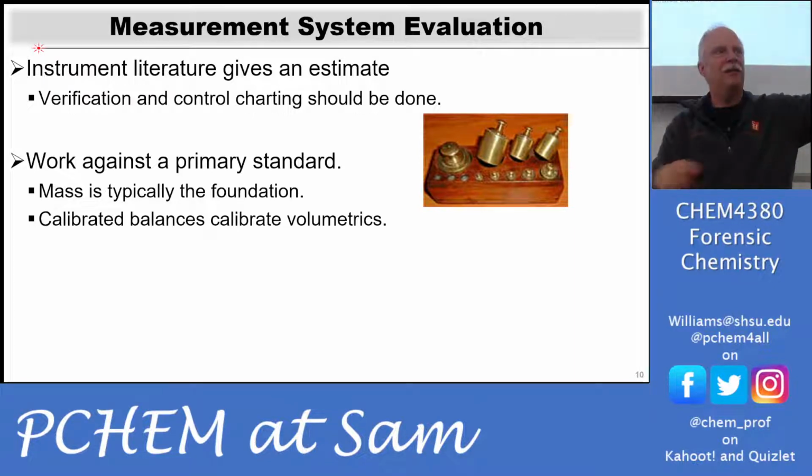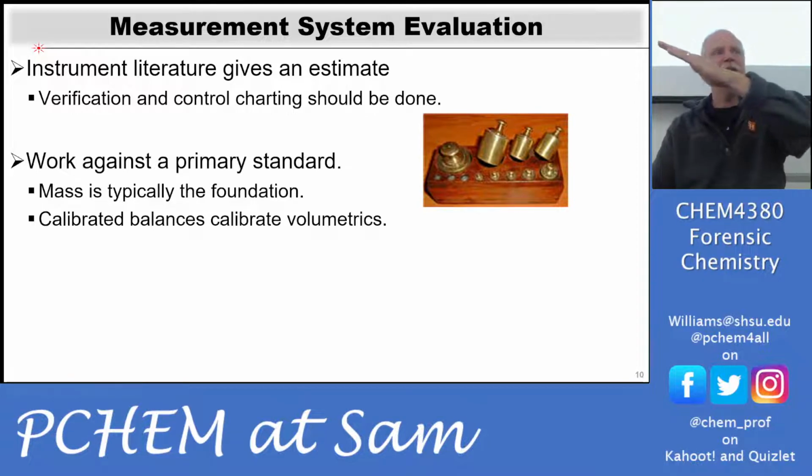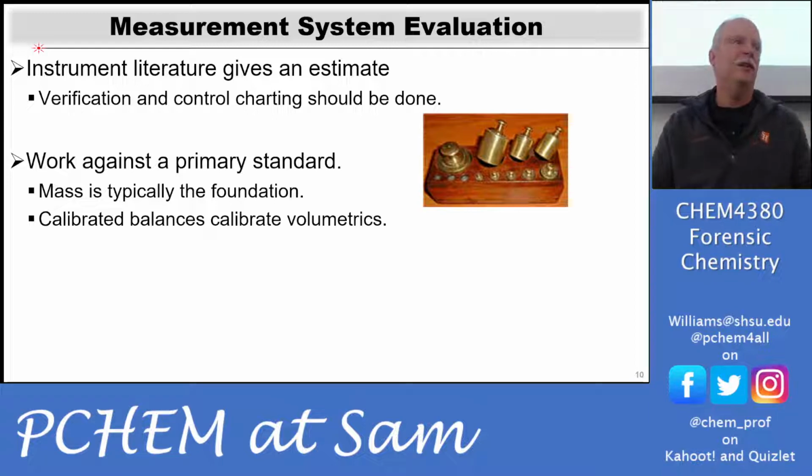And so every increment is supposed to be 10 microliters, and you're looking at the growth in mass. So you get mass per microliter, and you can see if that pipette is delivering what it says it's delivering. Over 20 measurements, you'll see if that slope is slightly less than it needs to be. Not only that, with your Excel skills in your ANOVA analysis and regressions, you can get uncertainties. So you can say that this pipette delivers X microliters plus or minus, and you can get from that ANOVA analysis your uncertainties in your pipettes.